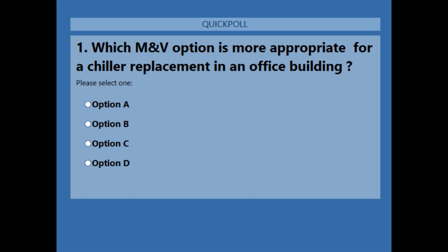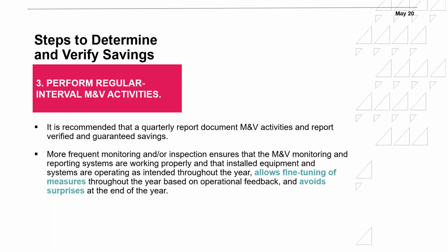So yes, option B is the correct answer for one chiller. Option C could be an option if that chiller is using a lot of energy, constituting more than 10% of the building consumption, which could be the case if there are only, let's say, 2 chillers in that building. So option C could also be used. I prefer option B because it's only one piece of equipment. Put all the measurements around it and get the savings on the chiller, because there are no interactive effects. You also save yourself a lot of adjustments in the building. You still need to do some adjustments, but it will be less of a headache than with option C.